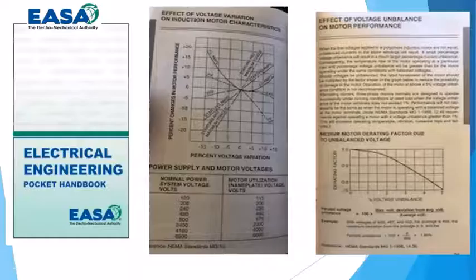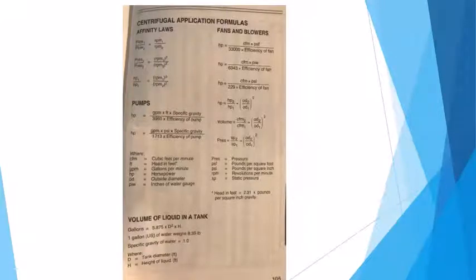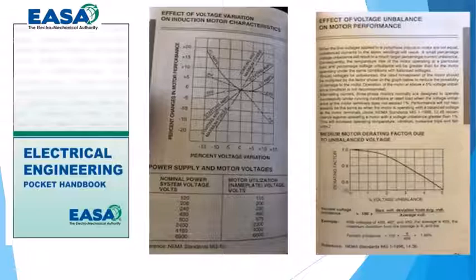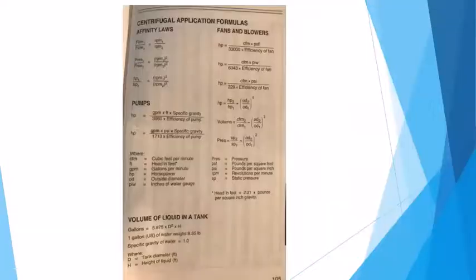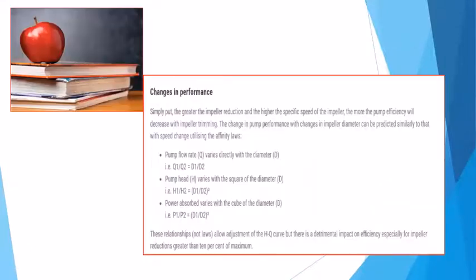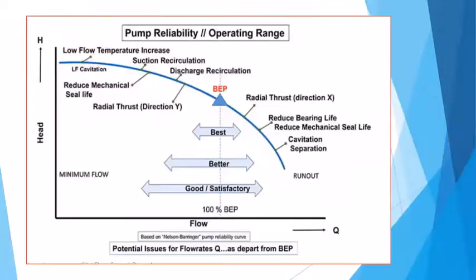There's a lot of drive controls, and I talk about VFDs, where they're changing the frequency and the voltage to the motor, but you've got to look at the total volume of liquid to get into the tank, the total volume of acre feet of water provided to the irrigation site. So don't be fooled that it appears it's drawing less, because it may take that much more time of that pump running. So your average power utilized will tend to be almost the same. And so what I really look at is what is your optimal efficiency of the system.